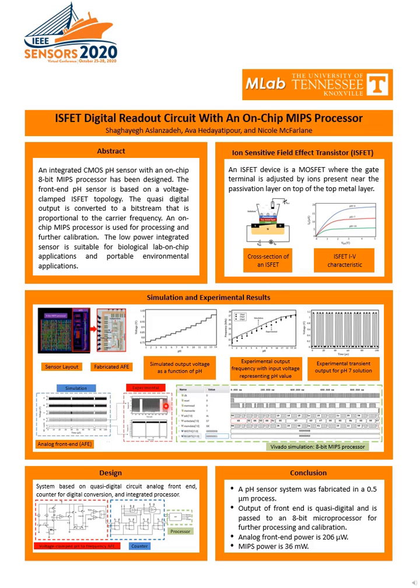The front-end ISFET pH sensor is based on the voltage clamping technique, whose output is converted to bitstream data. The average of the bitstream is proportional to the carrier frequency over a given time period. An on-chip MIPS processor is used for processing this bitstream data and for further calibration.